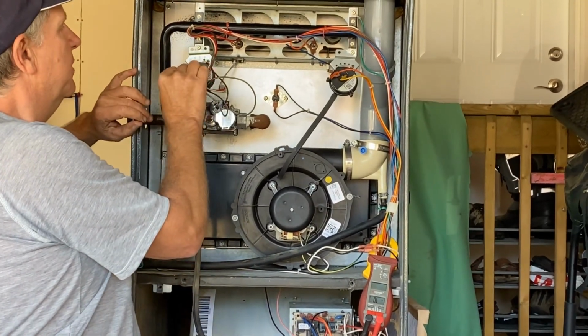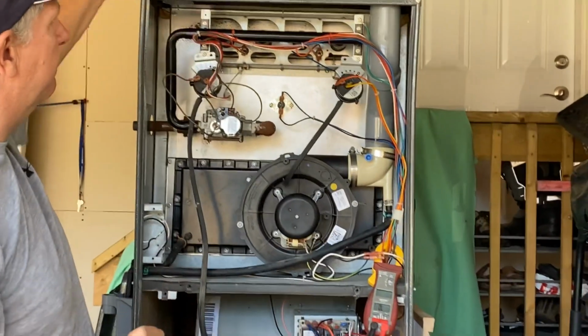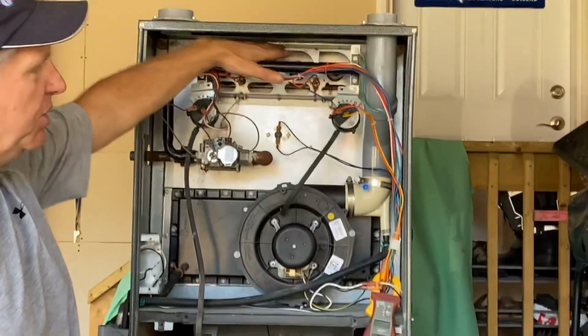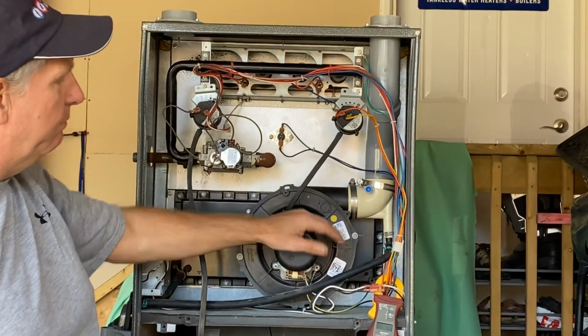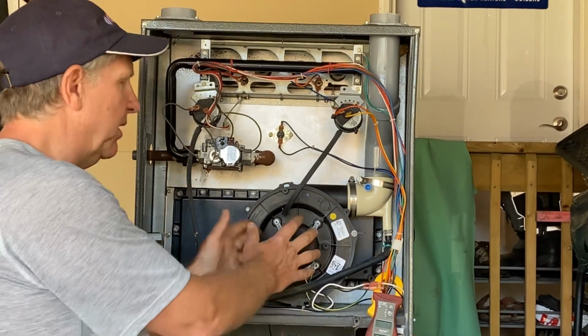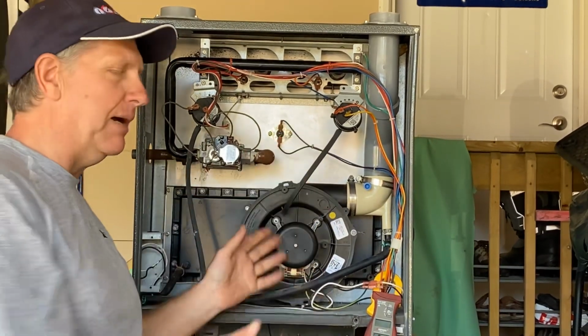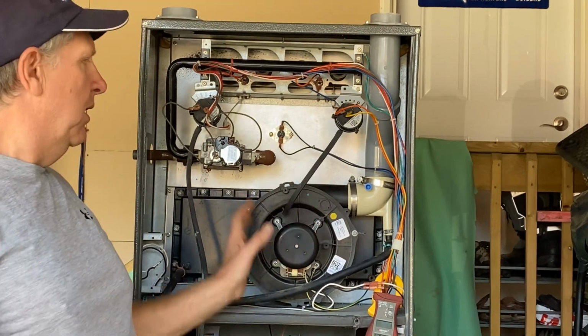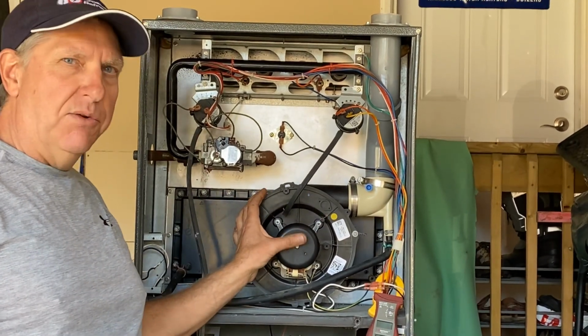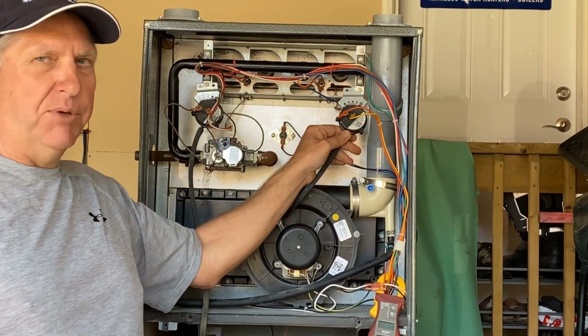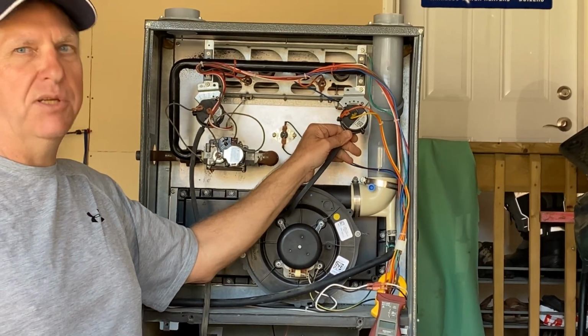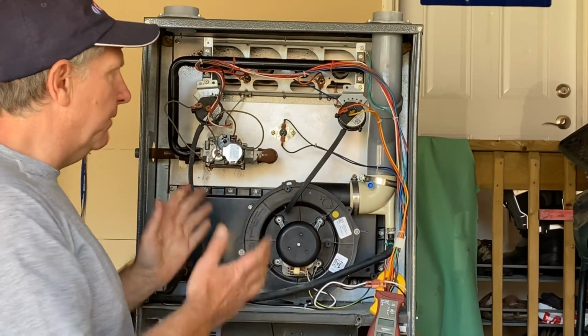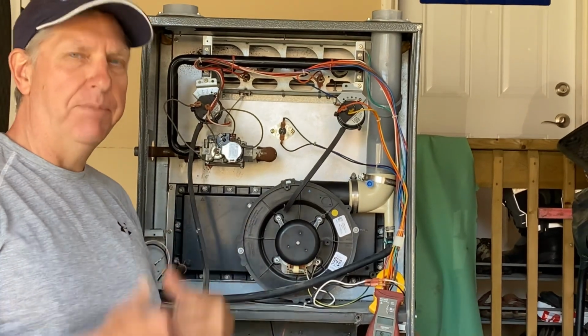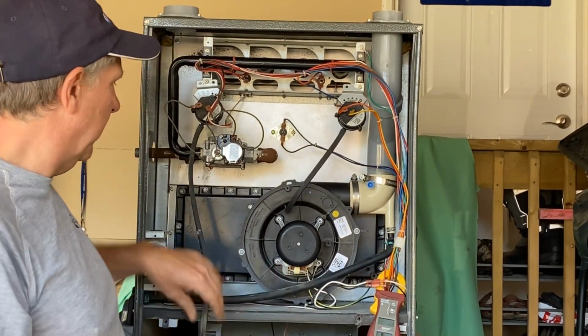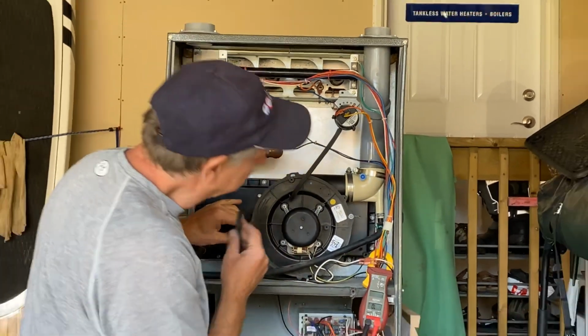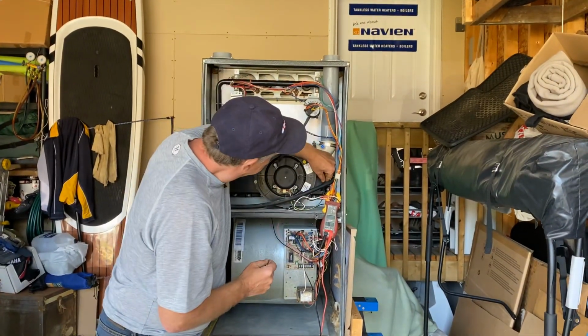But they are safety switches, and their purpose is if any of these plug up, if the heat exchanger plugs up, if this venter motor stops, if for some reason the motor is no good, plugs up, something inside breaks, whatever, if this induced draft motor doesn't run, there will be no negative pressure on these pressure switches, and you will not get a flame. It will not go through the flame starting process. Okay, so that's the pressure switch. That's when connected back over here.